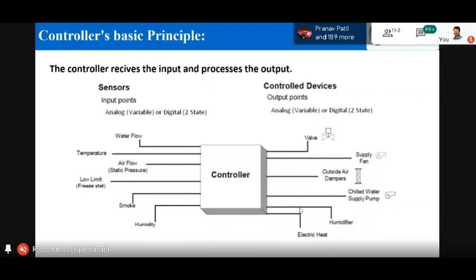These are analog inputs. This is again a very basic thing. Analog inputs are something which is a continuously variable signal like temperature, humidity, water. Digital is binary, on, off. If you want to know the status of the pump, it is a digital input. Or if you want to know the trip status, it is again a digital input. Then outputs, you have analog output. If you want to have a modulating valve, you have to have analog output going there. If you want to have VFD, you need to have analog output going there. Digital output is two-state. It is like lights on or pump on. So that is digital output. That was the hardware side of I/O.